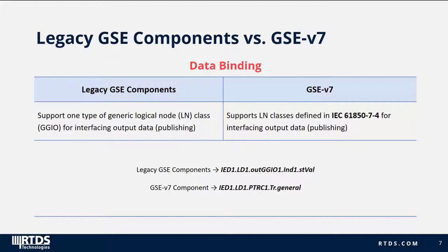In contrast, the same trip signal can be mapped to IED1/LD1/PTRC1.TR.general in GSE V7. Here, the use of the PTRC — Protection Trip Conditioning logical node class — explicitly indicates to the outside world that the mapped signal is a trip command. This type of virtualized and object-oriented data mapping is one of the defining principles of the IEC 61850 standard.